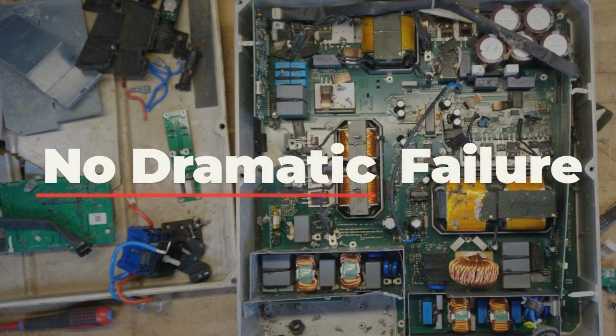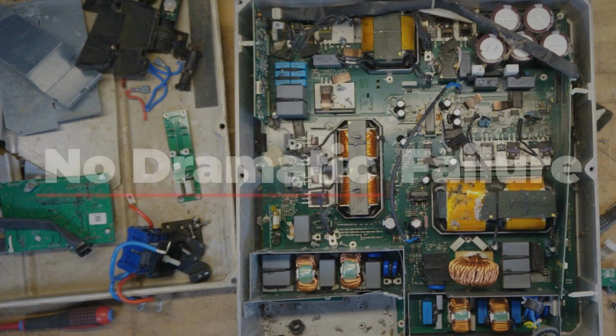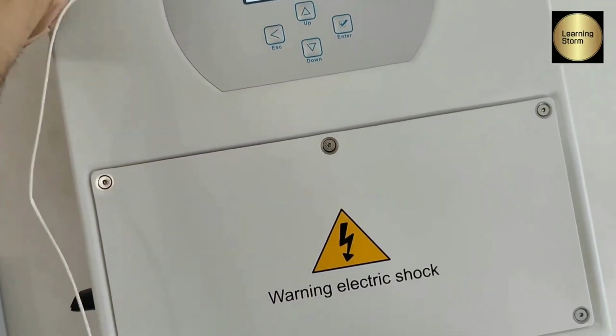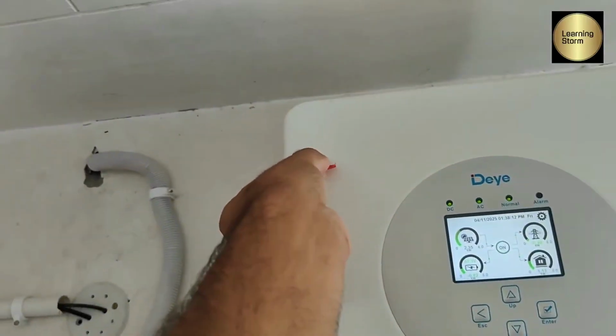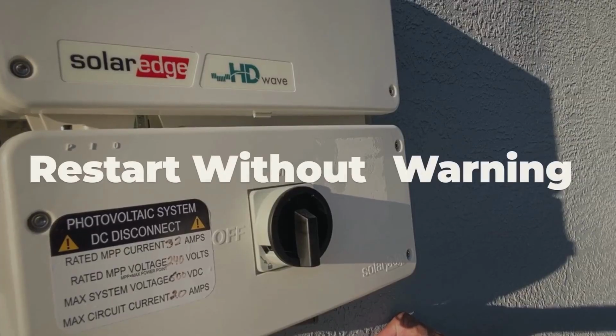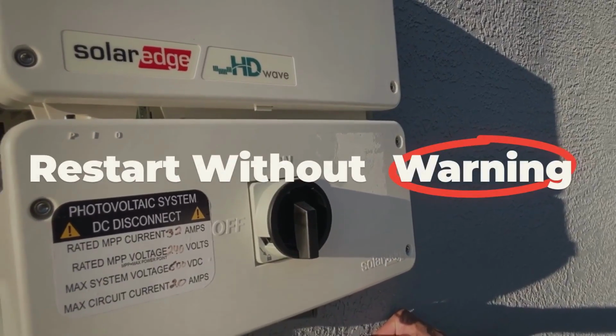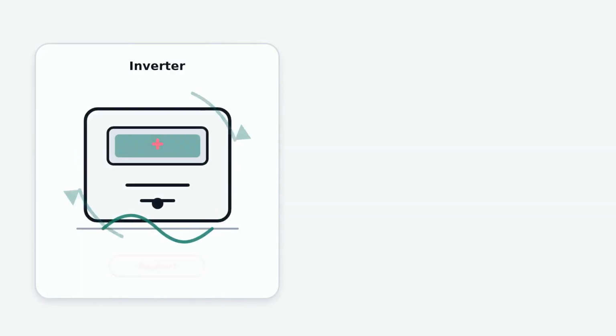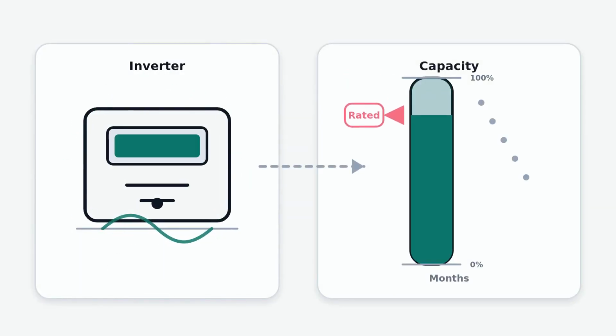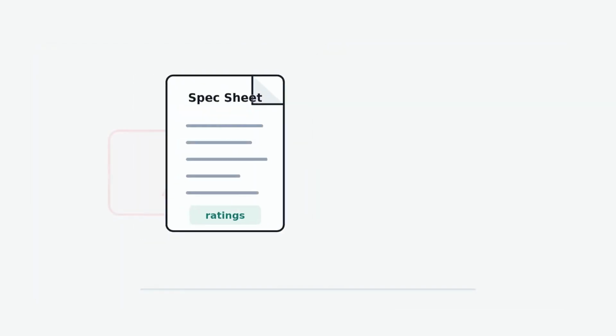Most inverters don't fail dramatically. No smoke, no pop, no obvious moment of death. They just quietly throttle output on a hot afternoon, restart without warning, then degrade across months until your system is running at 60% of rated capacity and nobody knows why. The spec sheet never shows you that.